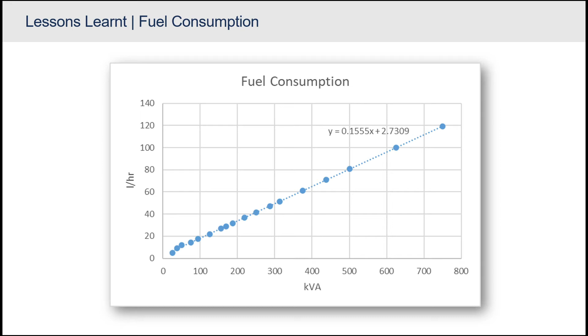It's not always just about size. You must also consider the load you put onto that generator. This is earmarked at about 80% load. If you use a lower load, you must use that load figure rather than the generator size. Just for interest, it's quite a linear graph that we ended up with.